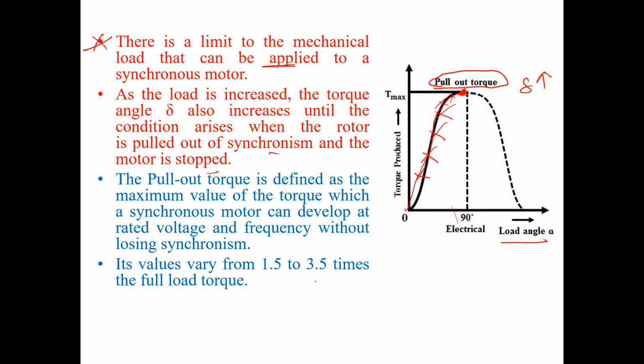The pull out torque is defined as the maximum value of torque which the synchronous motor can develop at rated voltage and rated frequency without losing synchronism. That means, above this, if the value of torque is above the pull out torque, the motor will lose its synchronism. Its value varies from 1.5 to 3 times that of full load torque, meaning this pull out torque is always more than full load torque.